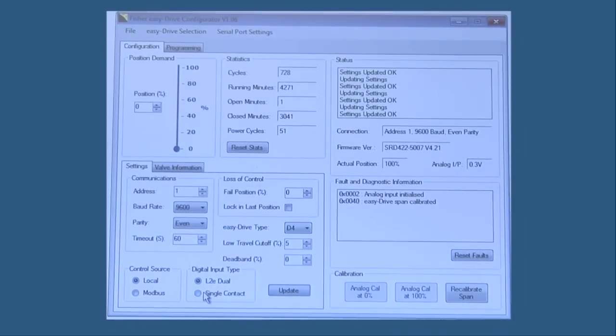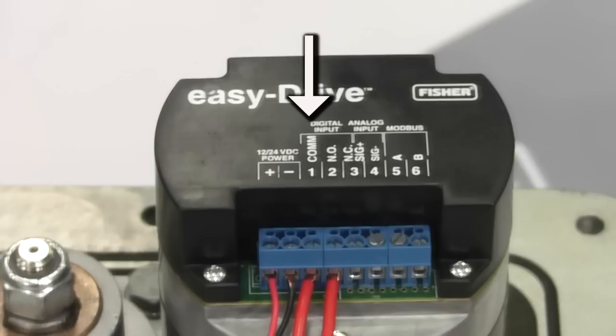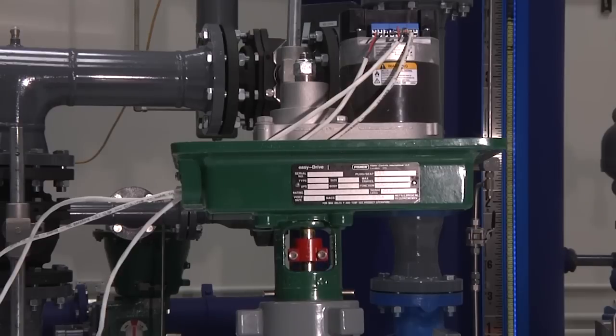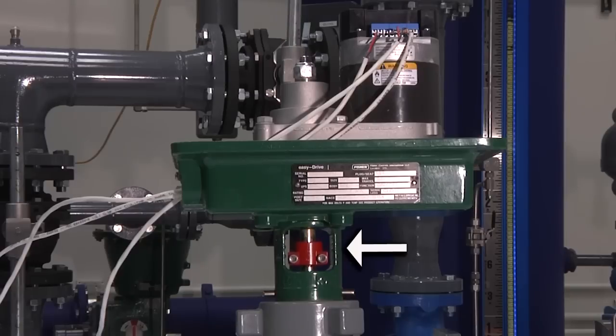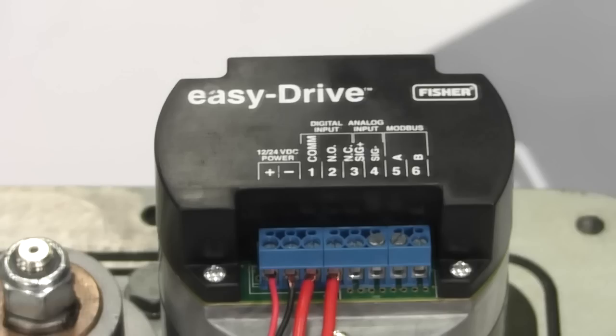For the first on-off mode, single dry contact achieves continuity across terminals one, the common, and two, the normally open. When these are in continuity or the voltage differential between these terminals is zero, the valve should respond by opening. Once the connection between the common and normally open has been broken, the valve should move to the closed position. Using these wires, we are demonstrating a contact closure.